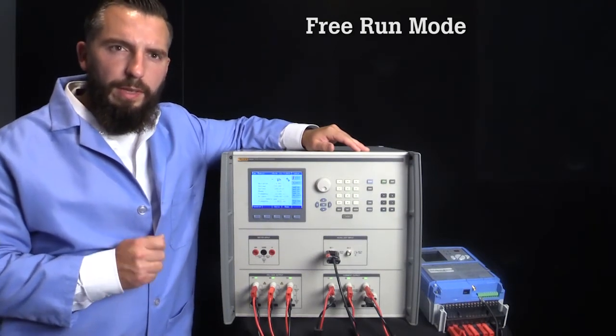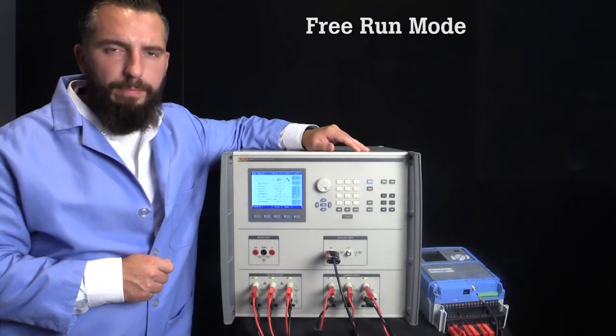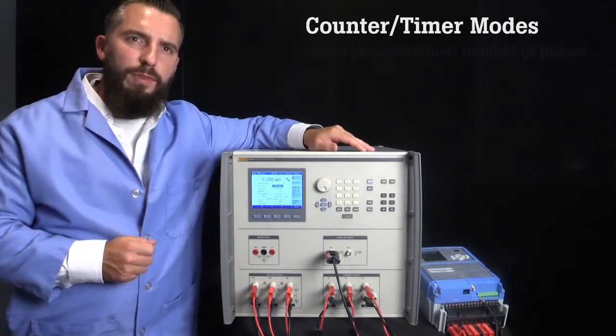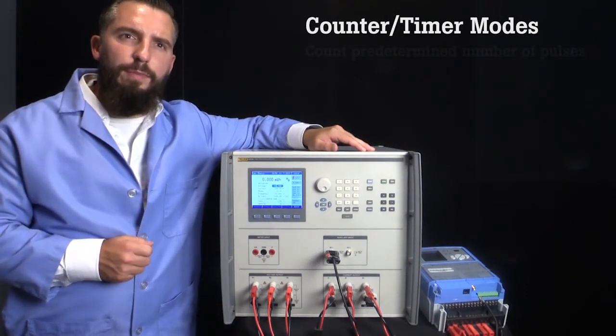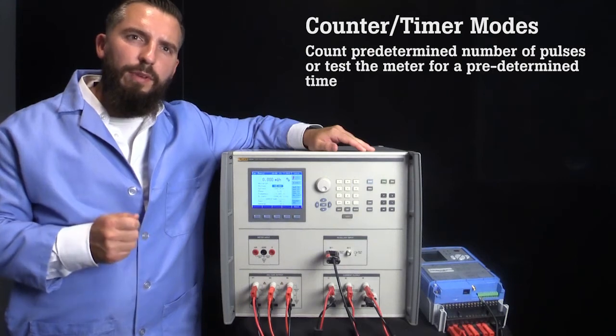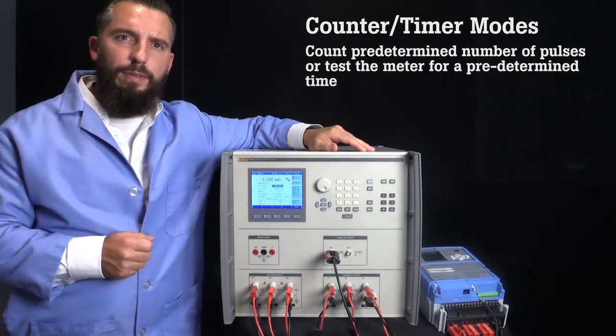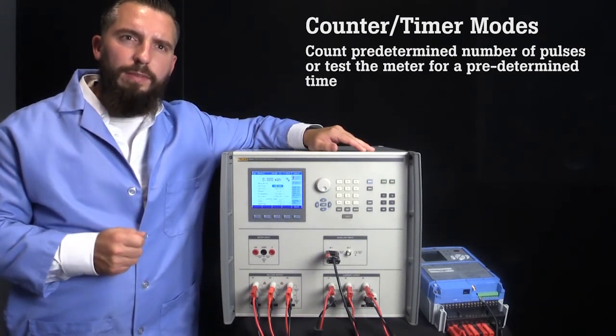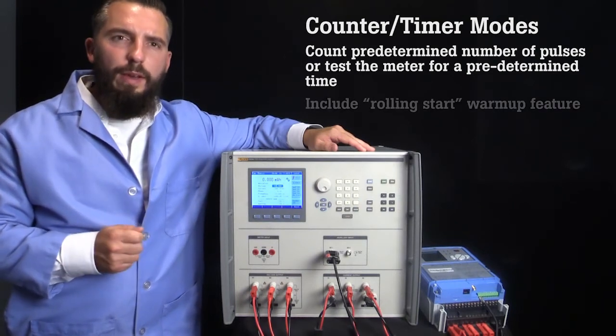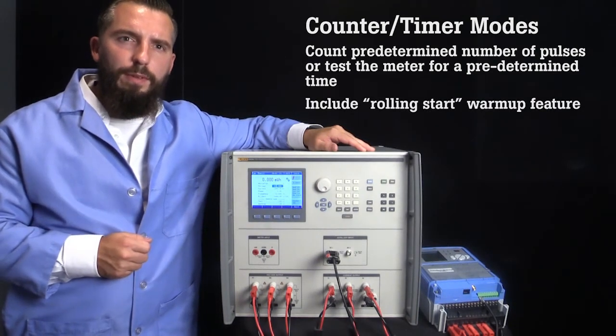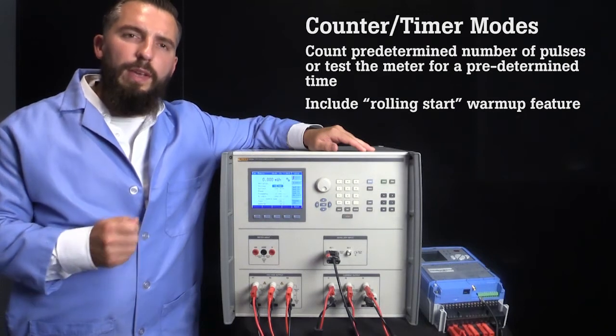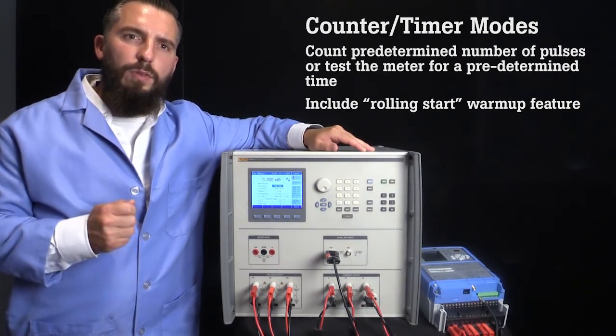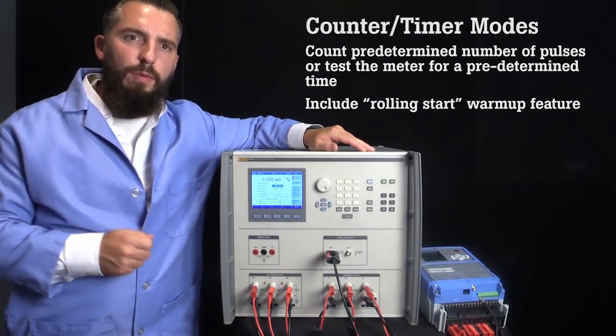For that, we recommend the counter mode or timer mode. The reason counter and timer modes are more repeatable methods to test energy meters is that they either count a predetermined number of pulses from the meter under test or they test the meter for a predetermined amount of time. Both the counter and timer modes have a warm-up feature for the UUT. This counter method is also known as rolling start method because of the warm-up feature.